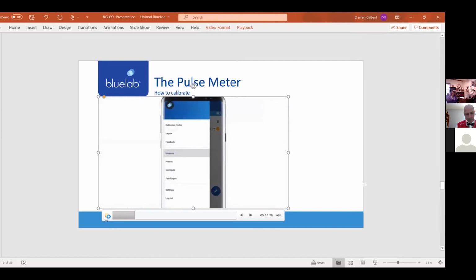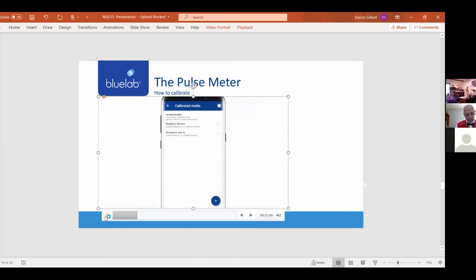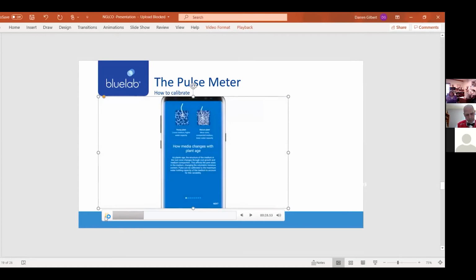Then you're going to take 5 readings. On the device itself there is a calibration mode, so it will walk you right through step by step what you need to do. You'll take 5 or 6 measurements, and it will average those out so you know exactly what your EC reading will be going forward, and then you've calibrated it to that medium.